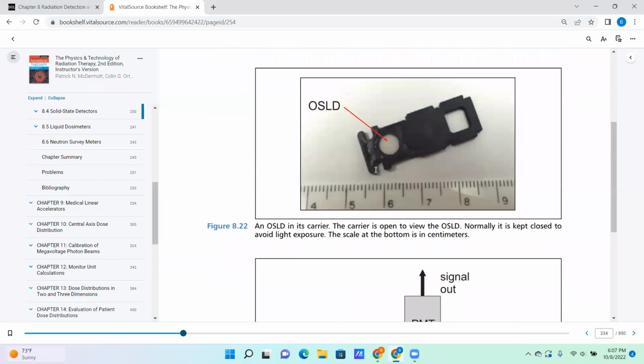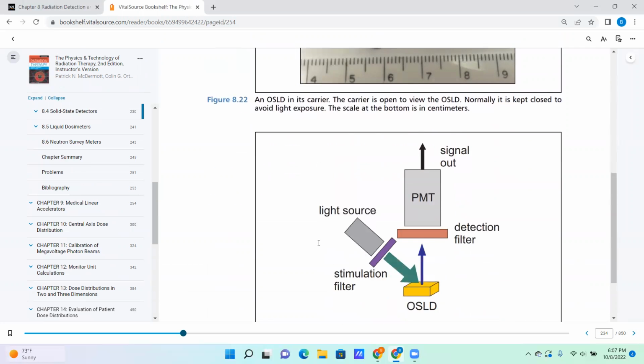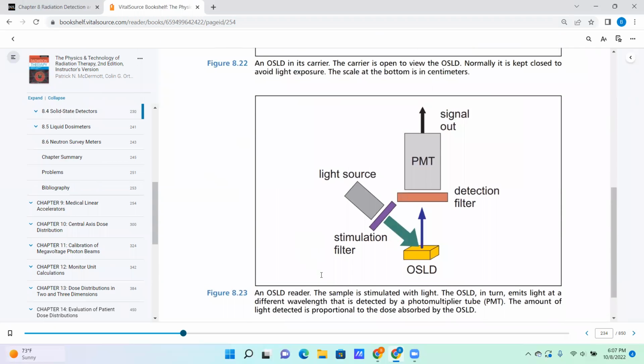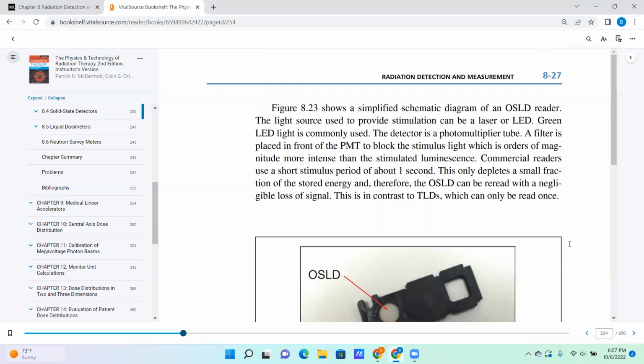So you can kind of see it here. There's an OSLD in its carrier, and the carrier is open to view the OSLD. Normally it's kept closed to avoid light exposure. If you've got a reader here, the sample is stimulated with light. The OSLD in turn emits light in a different wavelength that is detected by a photomultiplier tube. The amount of light detected is proportional to the dose absorbed by the OSLD. So this verbally describes a lot of the things that we just went through.